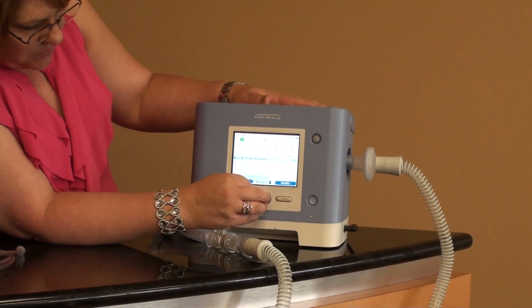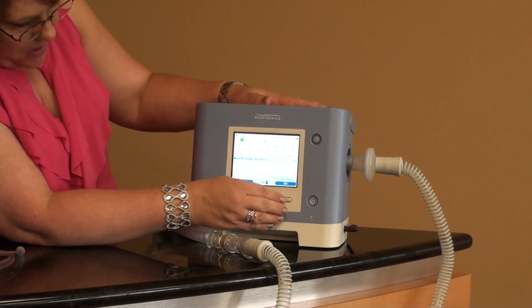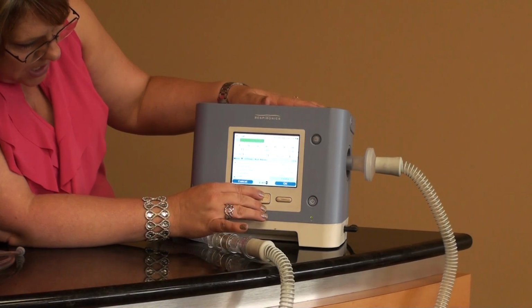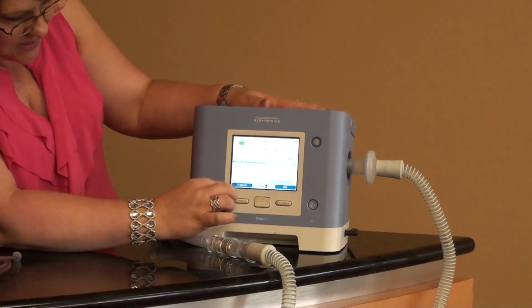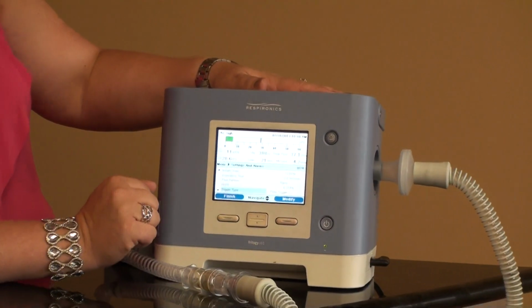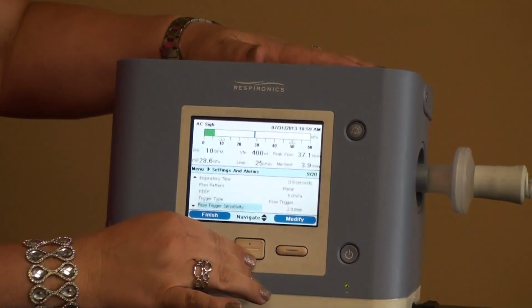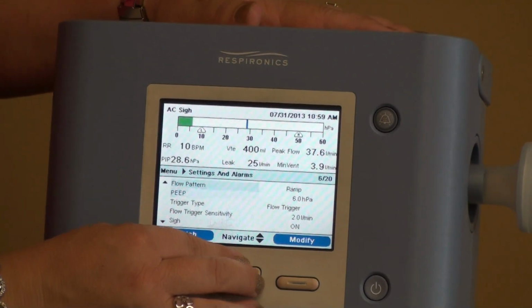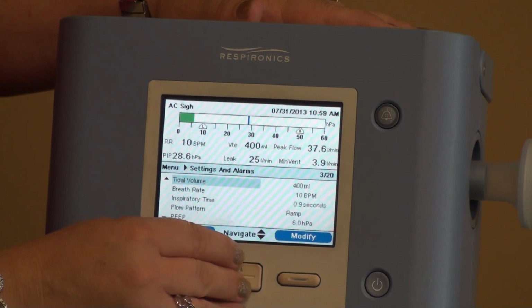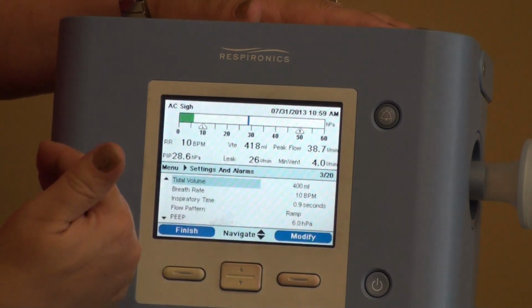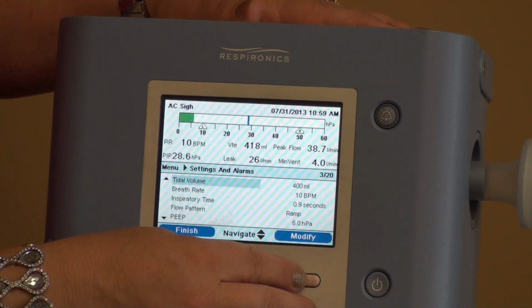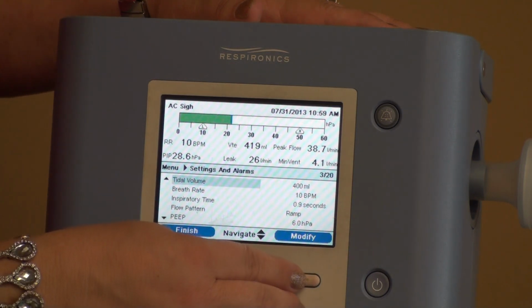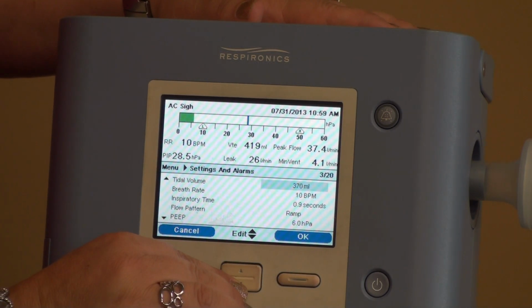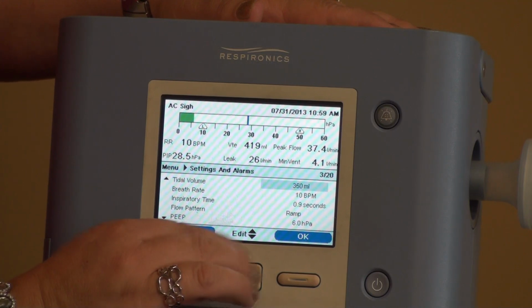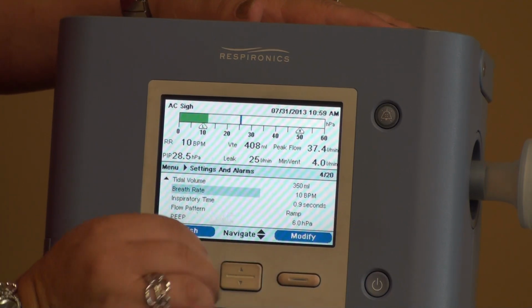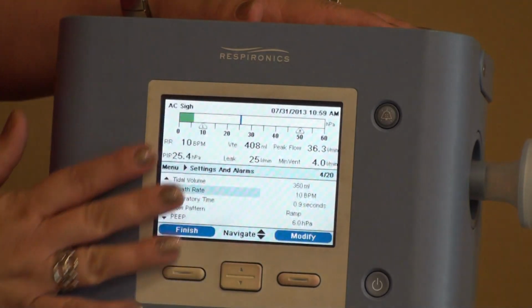Now, if I did want to change the PEEP, I would just highlight it, go to modify, and say I want to change it to 6. I would toggle until it said the number 6, then press OK, and now I have a PEEP of 6 in there. That is the same for every one of your parameters. For example, if the tidal volume needed to be changed to 350 according to an order, I would highlight tidal volume, modify, and it goes in increments of 5 until it reaches 350, and I would press OK. That's how I change all the parameters in here.